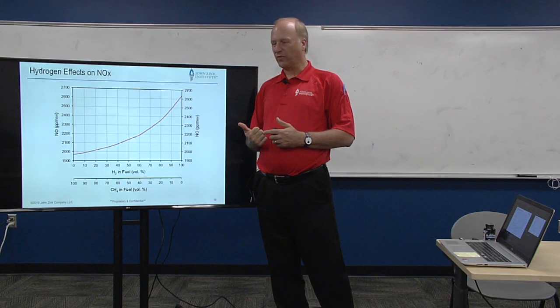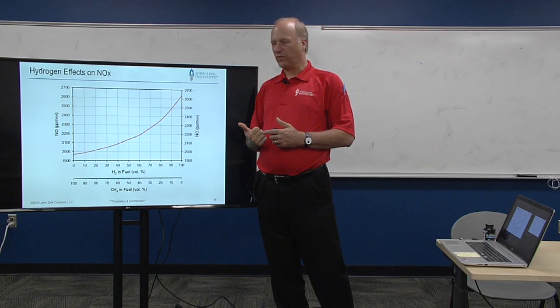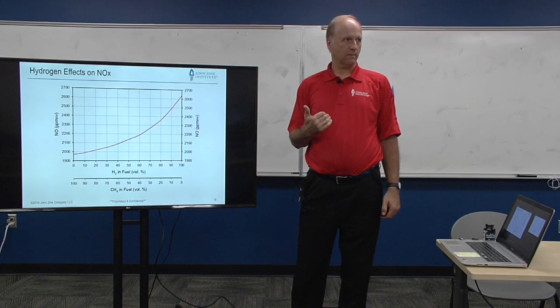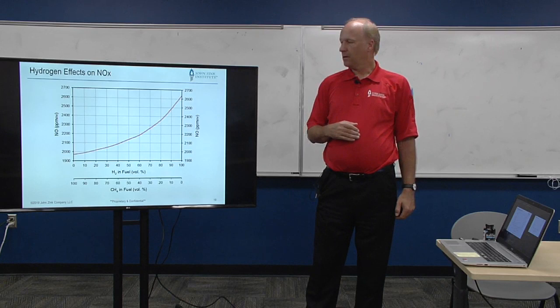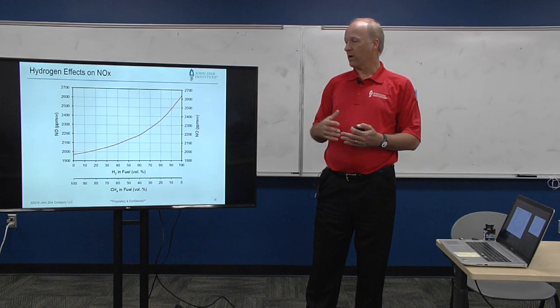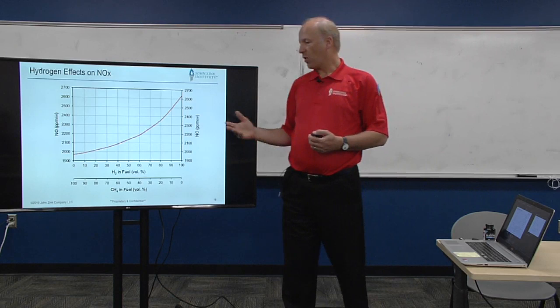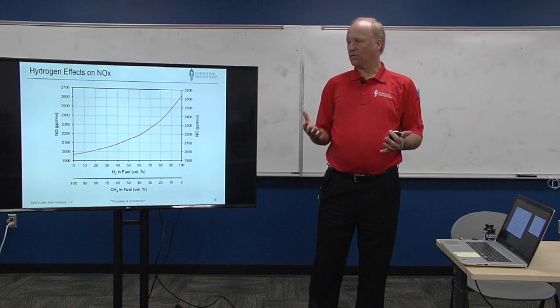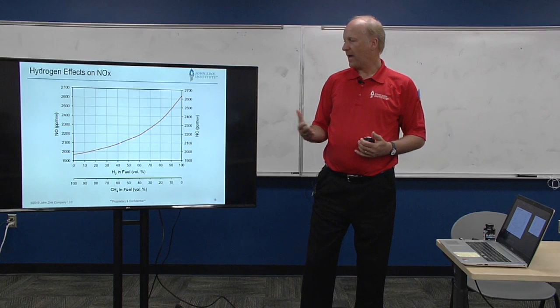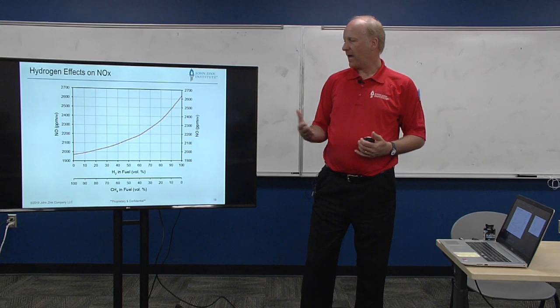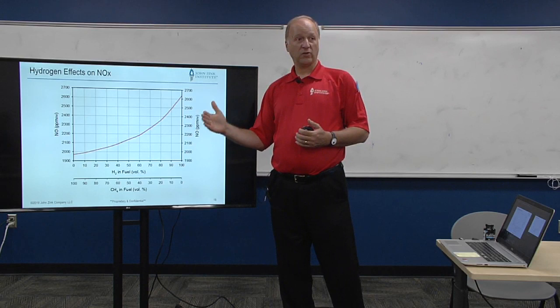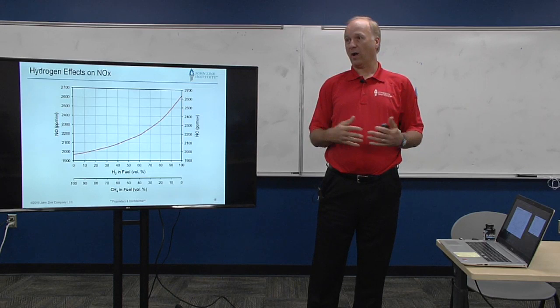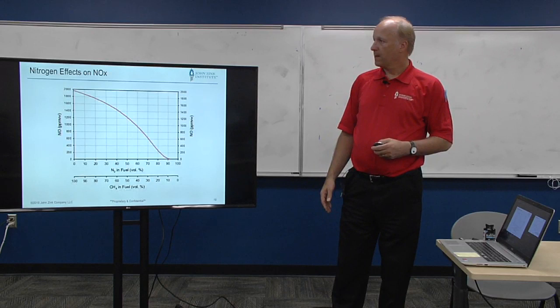Regarding hydrogen effects: hydrogen burns hotter than many other fuels. This plot shows a combination of hydrogen and methane — at the left it's 0% hydrogen and all methane; on the right it's all hydrogen and no methane. The more hydrogen, the hotter the flame, and the more NOx you make. When President Bush talked about a hydrogen economy, burning hydrogen makes water, which sounds good — except when you burn it with air, that air has nitrogen in it and you have to worry about NOx. If you burn pure hydrogen with pure oxygen you wouldn't worry about NOx, but of course you have to pay for that pure oxygen.